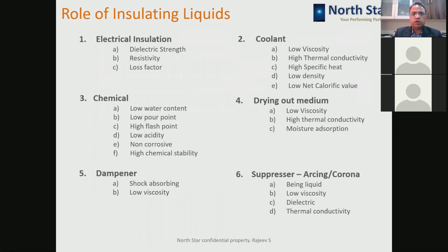And what role does an insulating liquid play, particularly in the case of transformers? So it plays six types of roles, starting from electrical insulation, then it acts as a coolant. It is a neutral chemical, so it provides an inert atmosphere inside the transformer. It should be a drying out medium because of its low viscosity and high thermal conductivity. It helps in taking out the moisture from the transformer components, especially solid insulation.